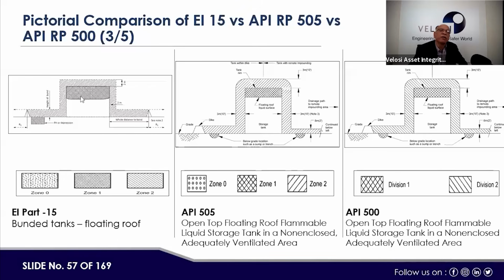If the floating roof is above the tank, it is zone 0, then here is zone 2, and some part is again zone 0, right? Zone 1 is not marked on the floating roof. Same is here. If you see, zone 0 is there and zone 2 is there, but zone 1 is not evident because that's against the nozzles. In a floating roof, there's no breathing valve where the hydrocarbon may escape.